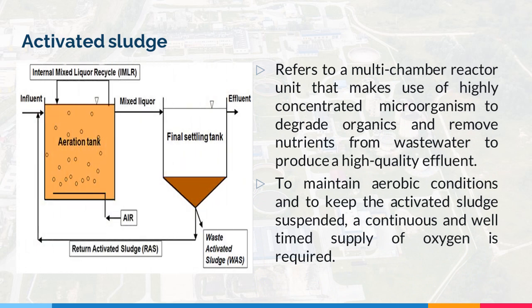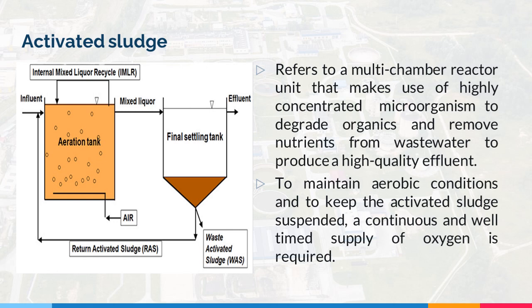One biological treatment is the activated sludge. It refers to a multi-chamber reactor unit that makes use of highly concentrated microorganisms to degrade organics and remove nutrients from wastewater to produce a high-quality effluent. To maintain aerobic conditions and to keep the activated sludge suspended, a continuous and well-timed supply of oxygen is required.